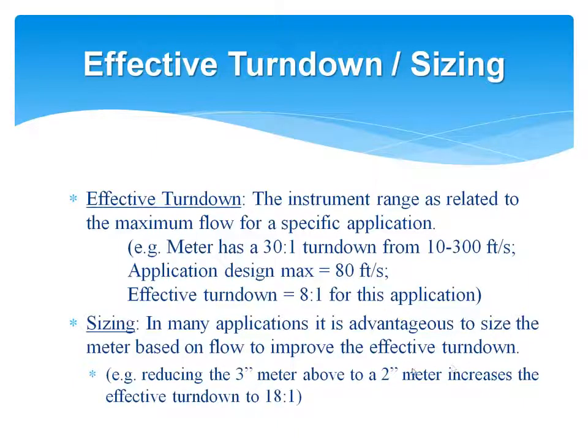That kind of leads us into talking about sizing meters properly. Meters should be sized really based on flow as opposed to based on pipe size. And again, with the same example, if we installed a 2-inch meter into that 3-inch application, you more than double your effective turndown, again, which would really enable you to measure a much wider range of flows and be able to measure partial steam loads.